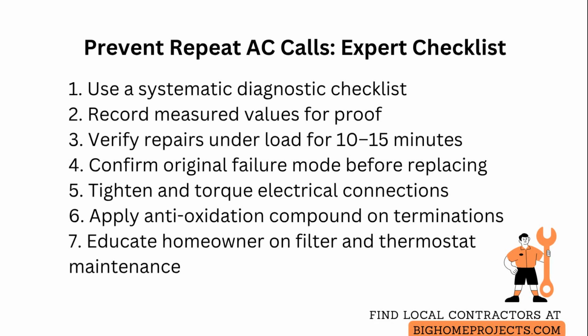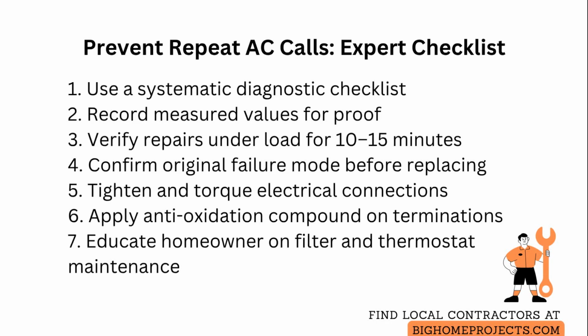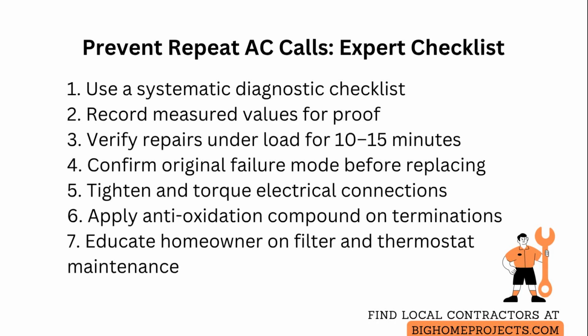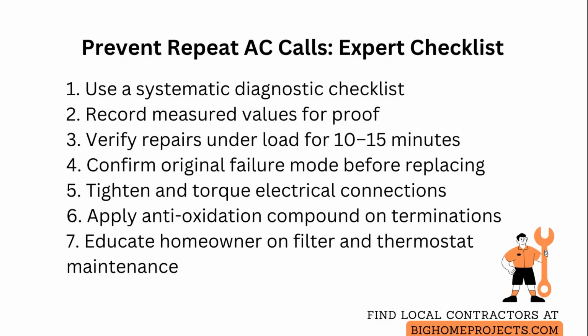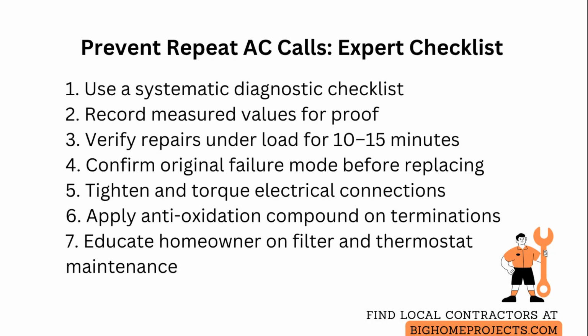When replacing parts, confirm the original failure mode so you do not exchange a component that was a casualty of another issue, and always test the system under load for at least 10 to 15 minutes to confirm stability. Tighten and torque electrical connections to spec and apply anti-oxidation compound on aluminum terminations to prevent future resistance heating.